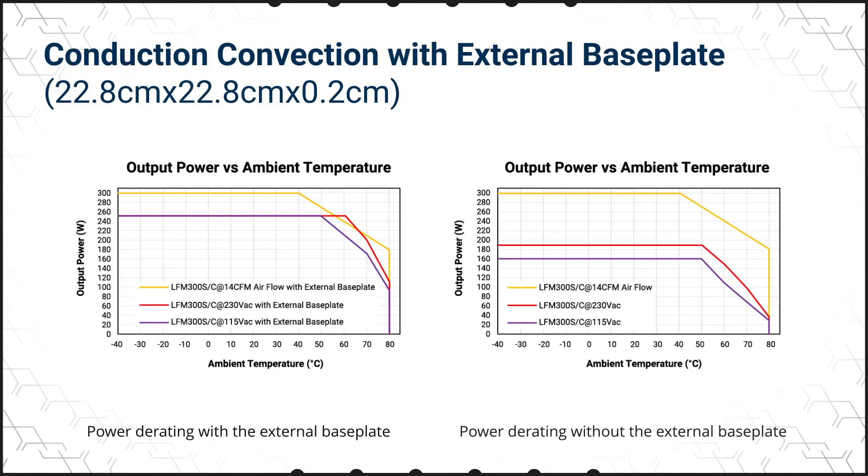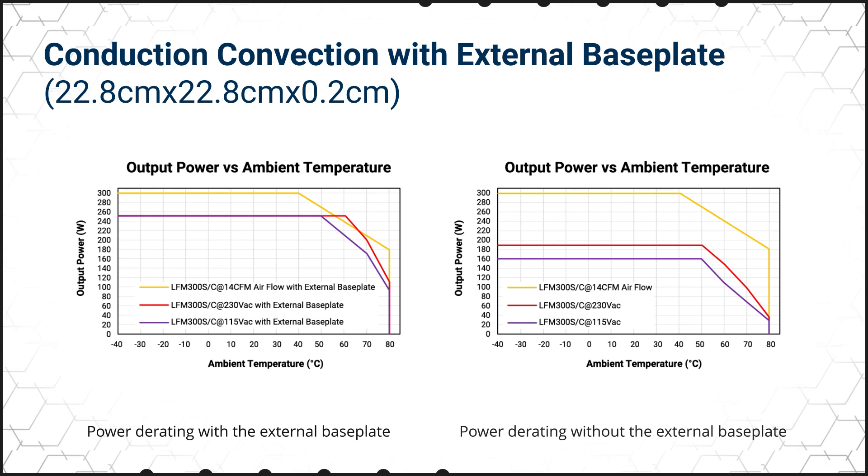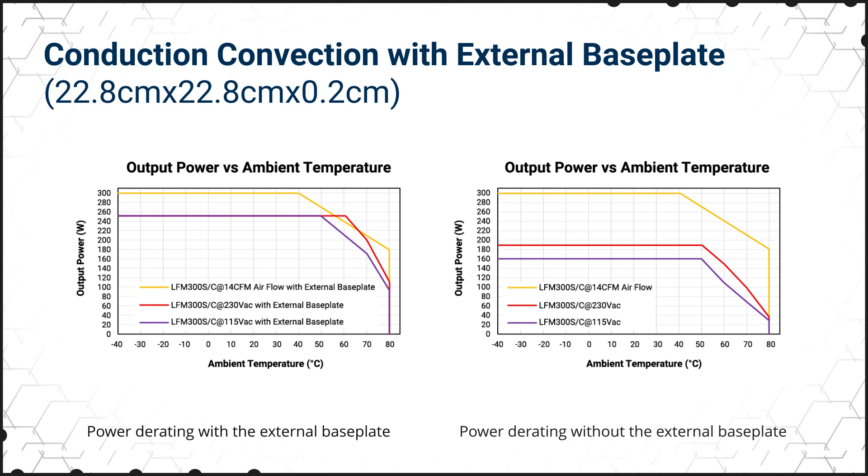Using an external base plate without a fan allows for a 250 watt output. With just natural convection cooling, the power output is limited to 160 or 190 watts depending on the input voltage.